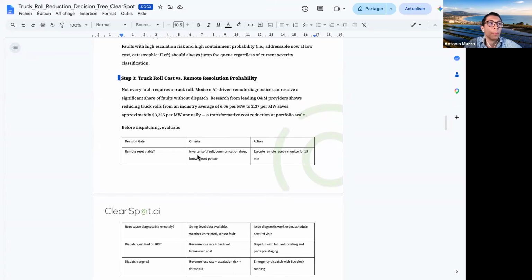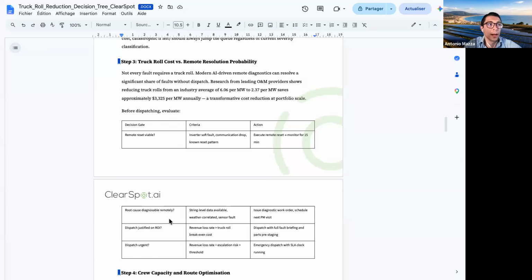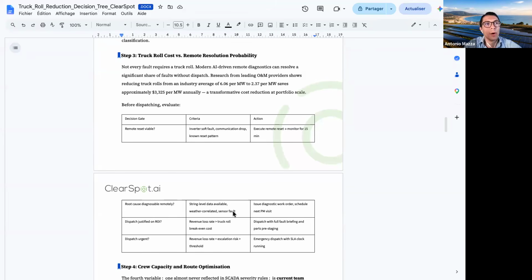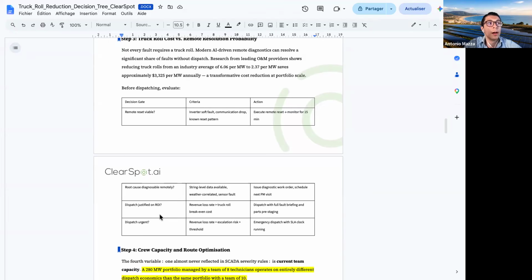So, is a remote reset viable? You should ask at this decision gate. Criteria versus action: inverter soft fault, communication drop, known reset pattern. Action: execute remote reset, monitor for 15 min. Root cause diagnosable remotely, string level data available, weather correlated sensor fault: issue a diagnostic work order, schedule the next PM visit. Dispatch is justified on ROI when the revenue loss rate is bigger than the truck roll break-even cost. Dispatch with full fault briefing and parts pre-staging.